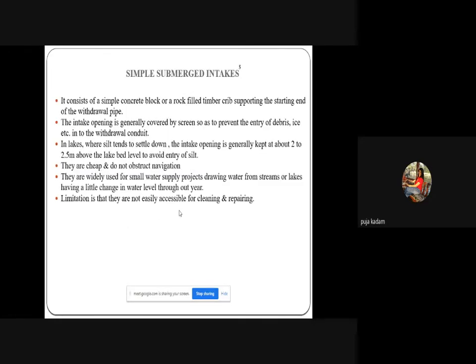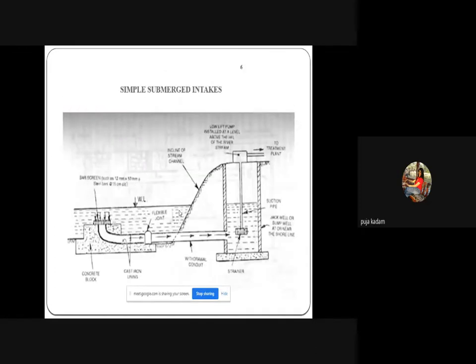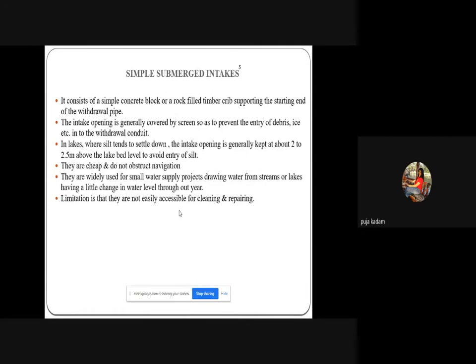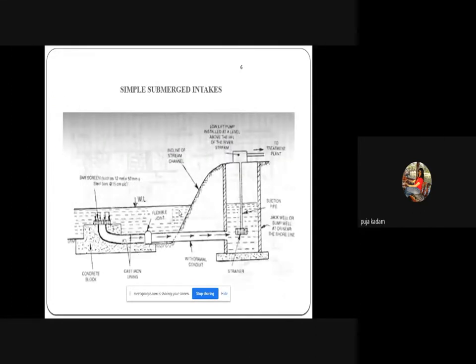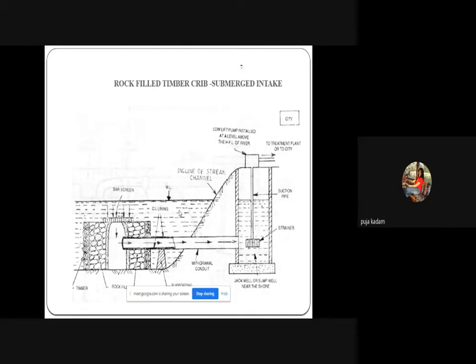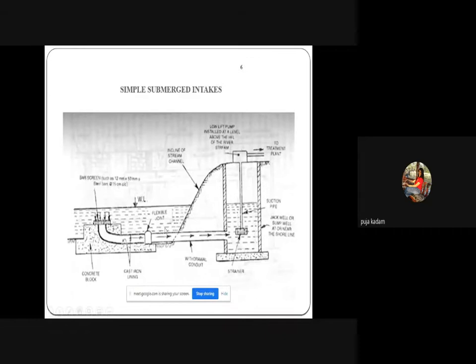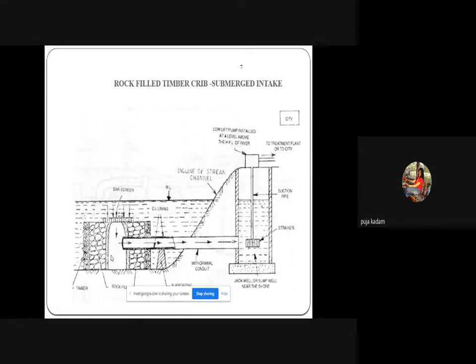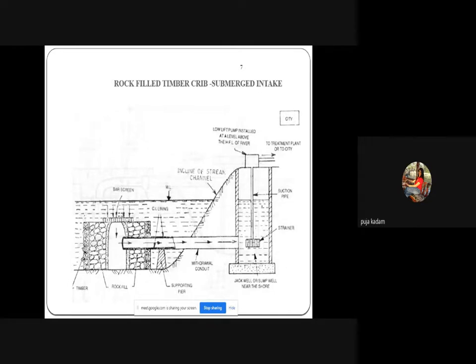A simple submerged intake structure consists of a simple concrete block or a rock-filled timber crib supporting the inlet end of the withdrawal pipe. A rock-filled timber crib is a wooden box structure filled with rocks, from where water enters the pipeline. The intake opening is generally covered by a screen to prevent entry of debris, ice, etc. into the withdrawal conduit. Screens are provided at the initial collection point of the water.